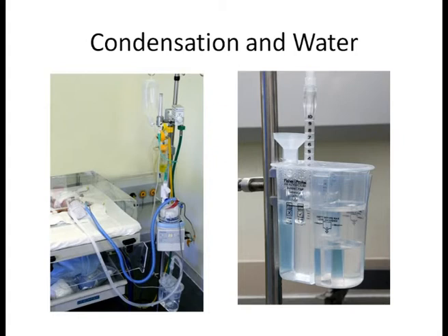If there is excess bubbling in the bubble chamber, that means the flows are too high in the circuit, and this may lead to inadvertently high pressure being delivered to the patient. So the bubbling should be adequate to generate the pressures, and the adequate bubbling is that which is minimal but present both during the inspiration and expiratory phase of the baby's breathing.